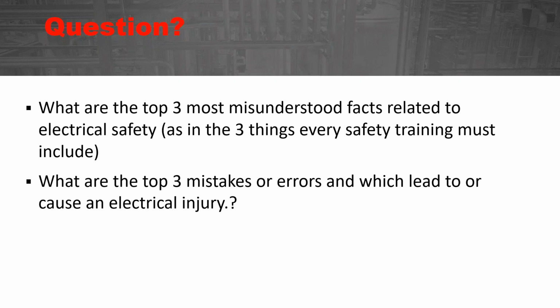Then you test for the absence of voltage. How do we do that? Test phase to phase and phase to ground of all the conductors and circuit parts. And a lot of times when I'm doing the hands-on training, the electrician or maintenance people or whoever, even safety people that I'm working with, they want to put down the meter at that point, and I'll say, oh, wait a minute, is your meter still good? And just a couple of weeks ago, I had someone say, oh yeah, it's good. How do you know? Well, the lights are on.